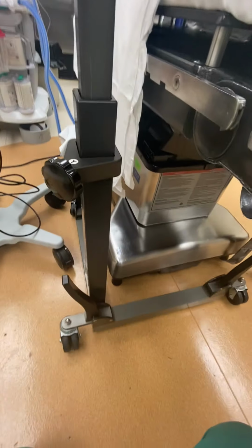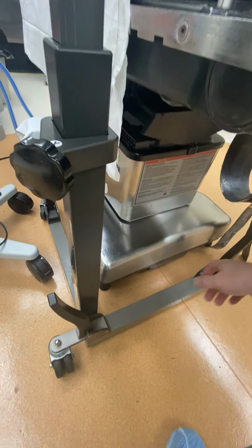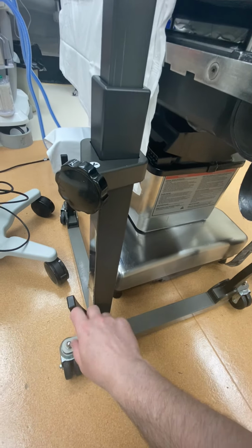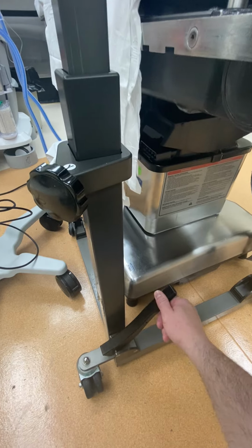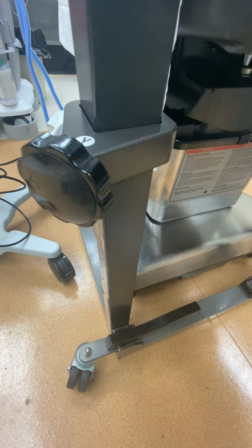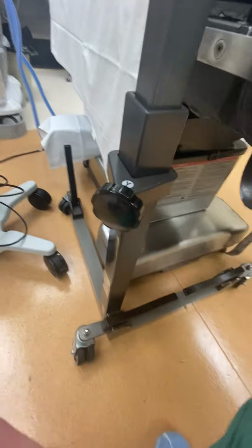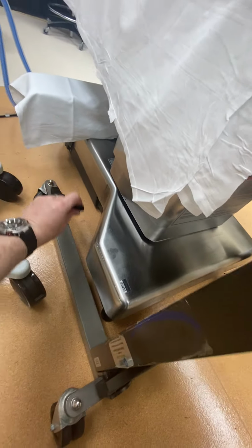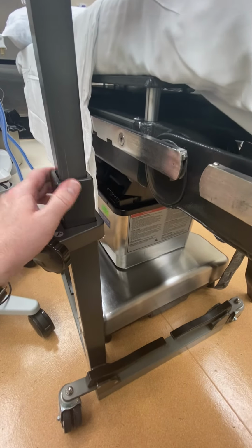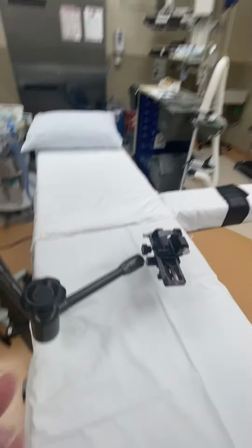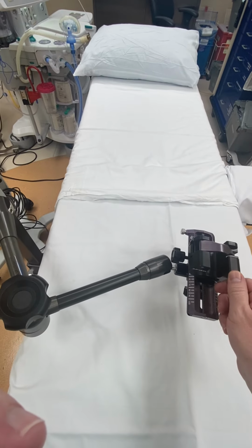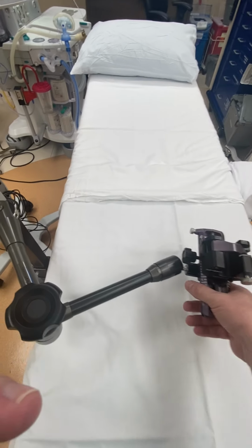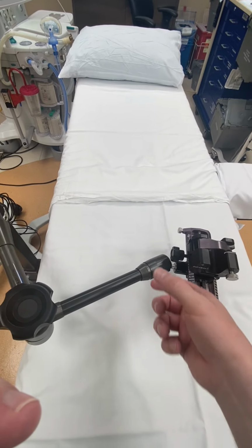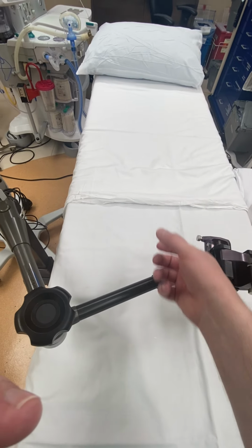There are 3 locks on the base, and you have to be careful because it drops by a couple inches when you lock it. You can watch here as I lock it, it'll drop. So we don't want to insert the probe before we lock it, because the probe could drop in the rectum and injure the patient. After you've locked all 3 locks, the base is stabilized. You can then dock the probe into the cradle, lock it in, and have the urologist, by holding the cradle and unlocking this bolt, insert the probe into the rectum just by moving the whole arm with the cradle into the rectum.